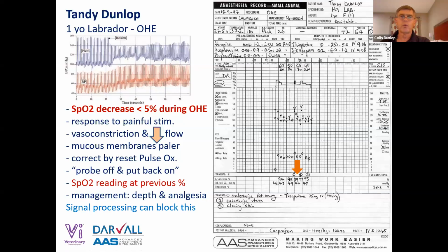Is it real? Well, one way we can test to see it's real, if that was a critical drop down to say 85, the first thing we should do is look at the patient, make sure the animal is pink, has a pulse, and is breathing. The next thing we could do is say, well, we think this is a response to surgery. We could take the probe off, the sensor off the tongue, put it back on the tongue. And sometimes people say that's because the sensor's squashing the tongue. What you're actually doing is resetting the background light absorption calibration on that machine.